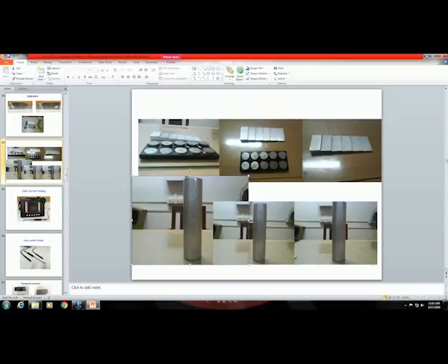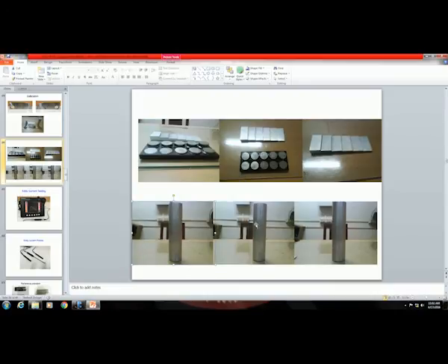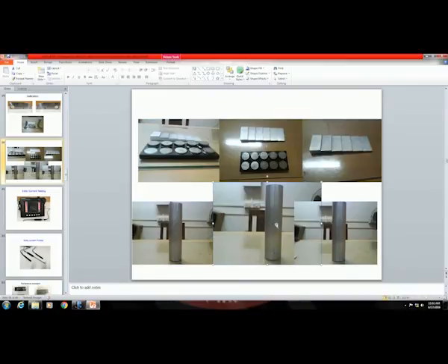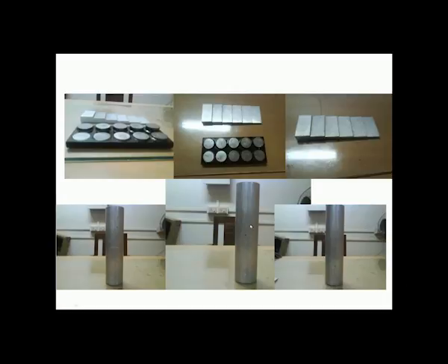Okay. On the time base you can see that, and you would be able to see some other holes also which are made at some other distances, because you need to collect the data at different distances to come up with the calibration curve or to do the calibration. So, here again you could see around this area, okay, there is another hole.